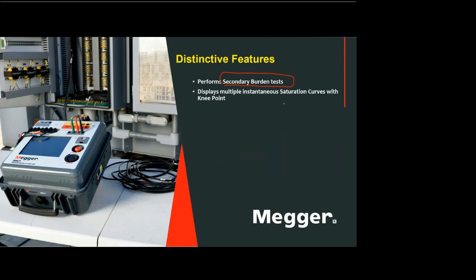So it displays multiple instantaneous saturation curves. If you have 5 taps, then you can see 5 curves. And the good thing is that it has an integrated 1 kV DC insulation test. You don't have to bring your Megger instrument for insulation because it has a built-in 1 kV DC insulation. It is compliant with ANSI C57.12.90, C57.13.1, and IEC 60044.